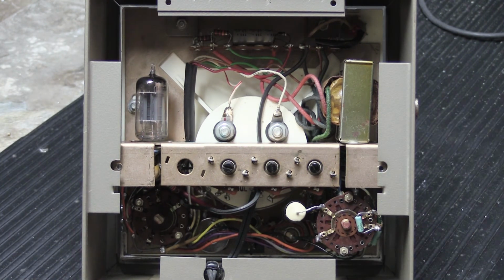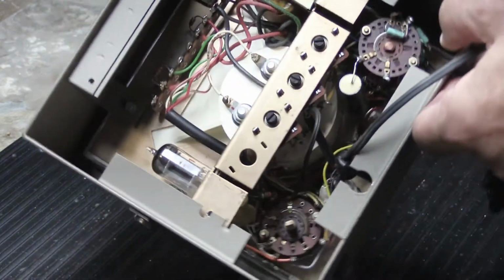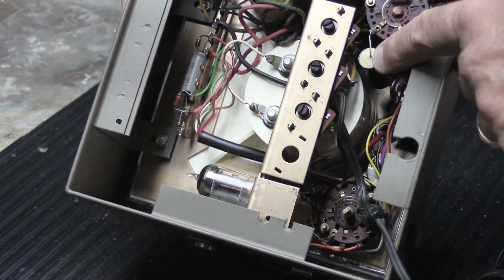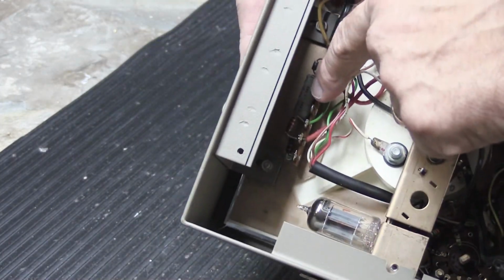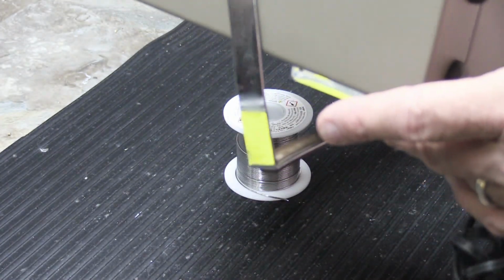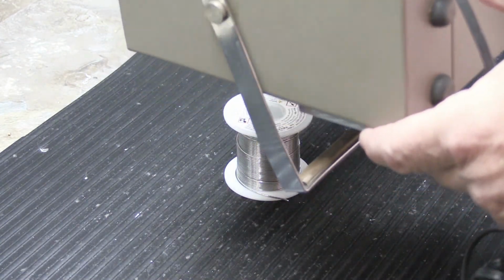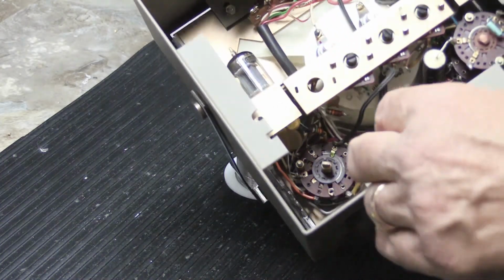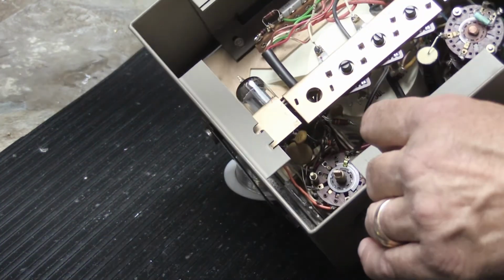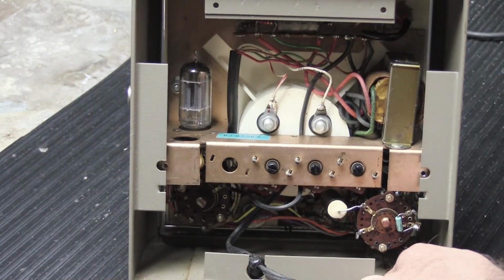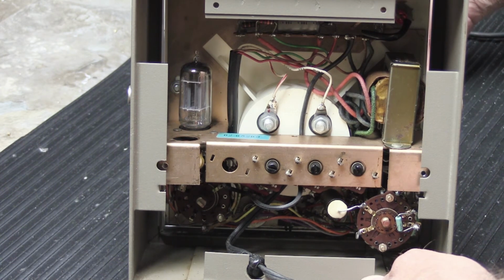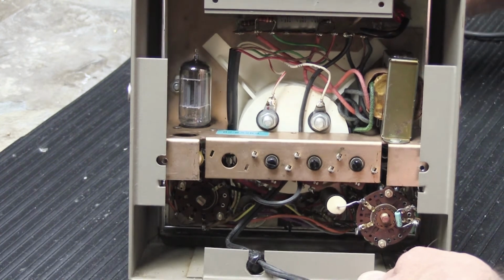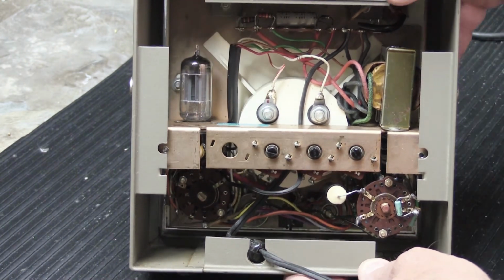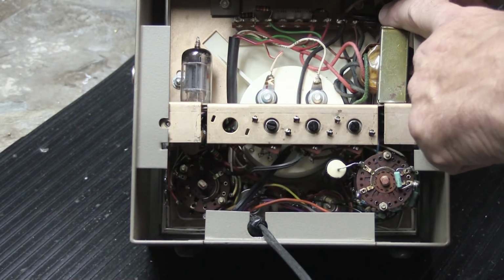There are a few capacitors that should be changed, and I think you can see one here, and there's one up here in the top. And I think there's one other one that's kind of buried down inside. Those will get changed out just because of their age. They're probably okay. The thing about equipment like this is if they see a lot of use, it can rack up into the thousands of hours, but it's not the kind of device that's left on 24/7, so it probably doesn't have hundreds of thousands of hours, but it makes sense to do that. So clean the switches, replace a couple capacitors.